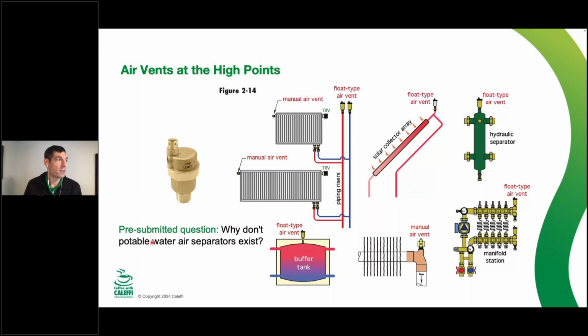We had a pre-submitted question, why don't you see potable water air separators? So there is a potable water air vent that we have in our catalog. This is called the plumb vent, and it is low lead. So if you did want to put one at the top of a plumbing riser that was having air issues or something like that, this one is capable of doing that. But most of the time, since these are all hydronic examples, you're going to see more air vents in a hydronic system than you would in a plumbing system, but it is an option.